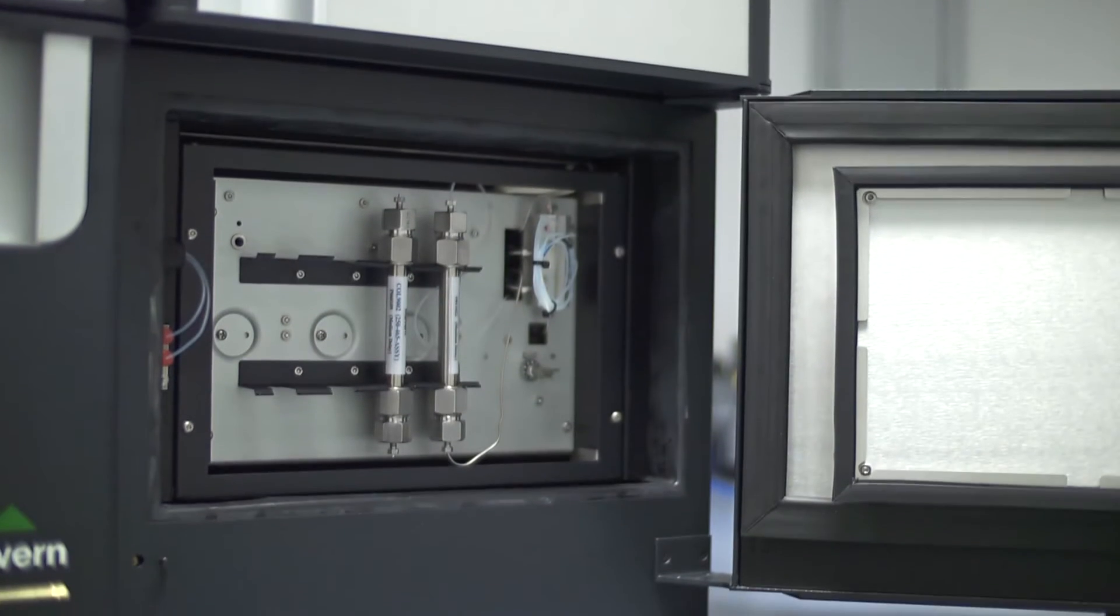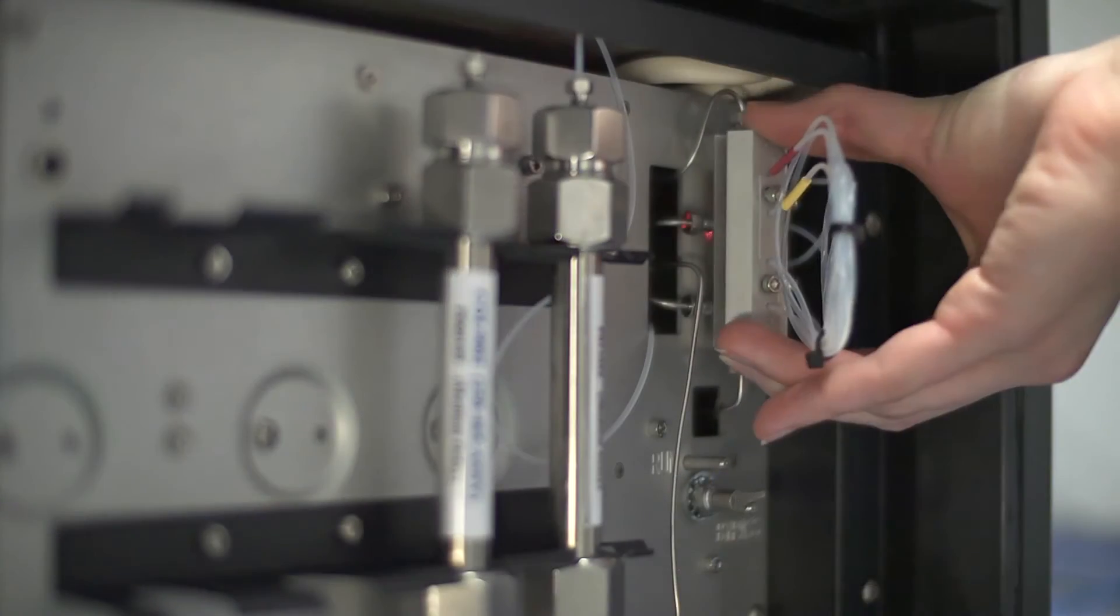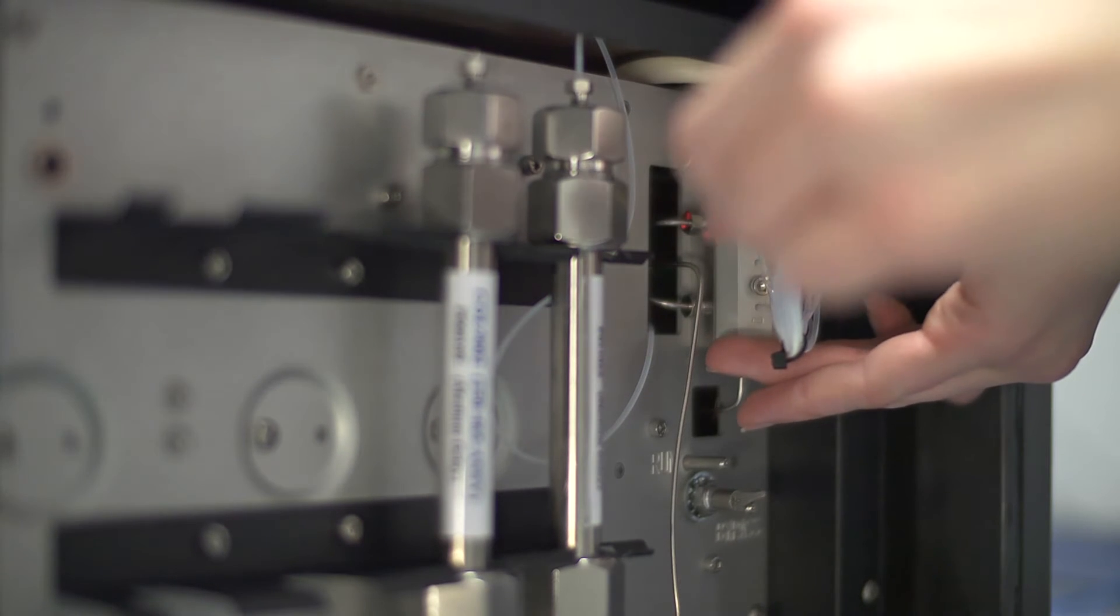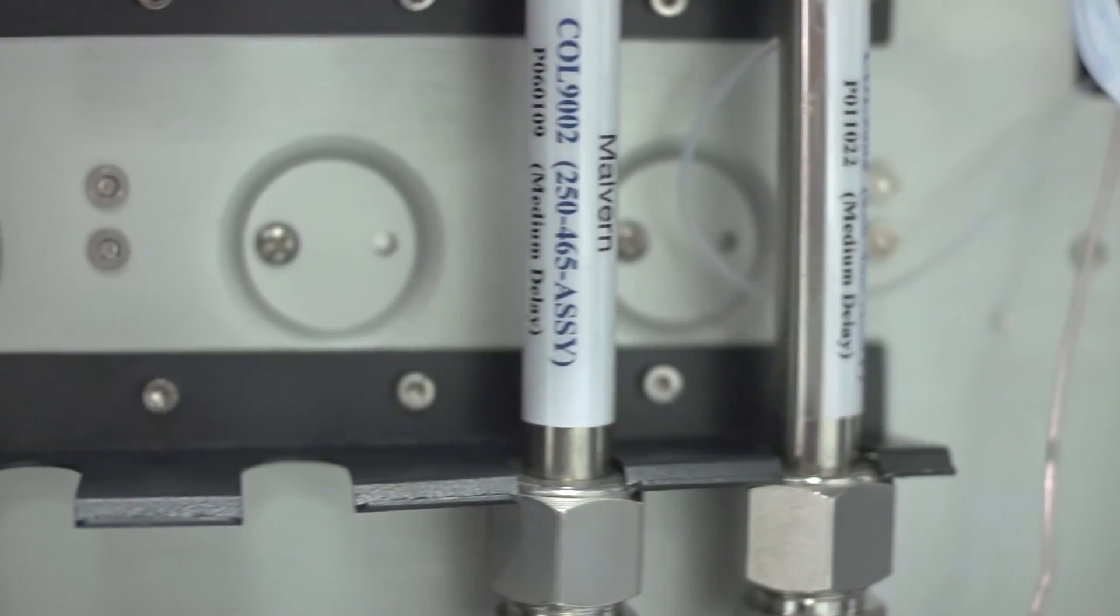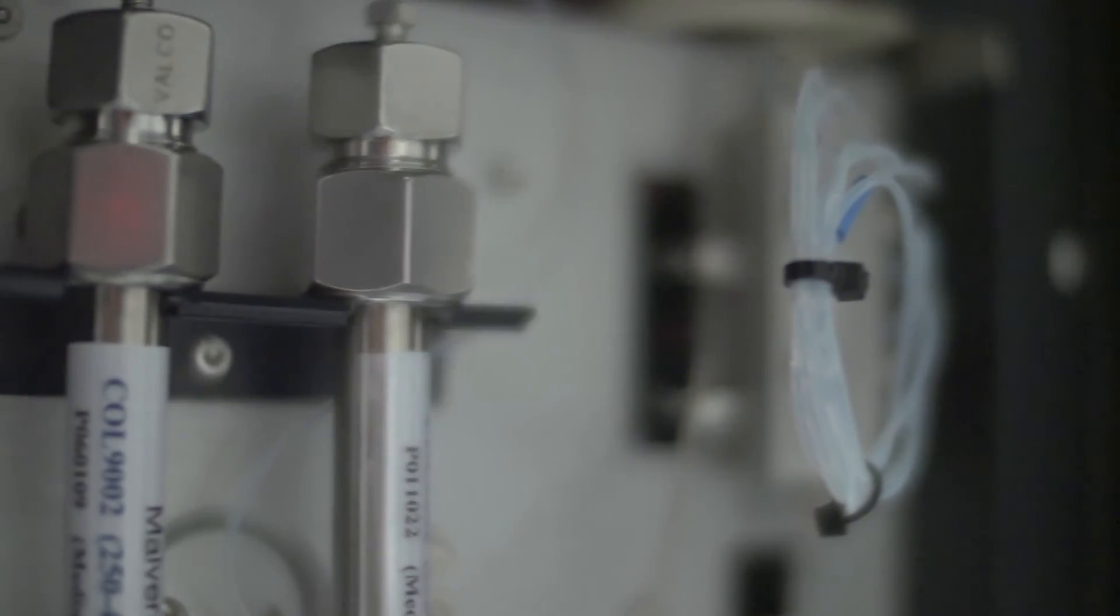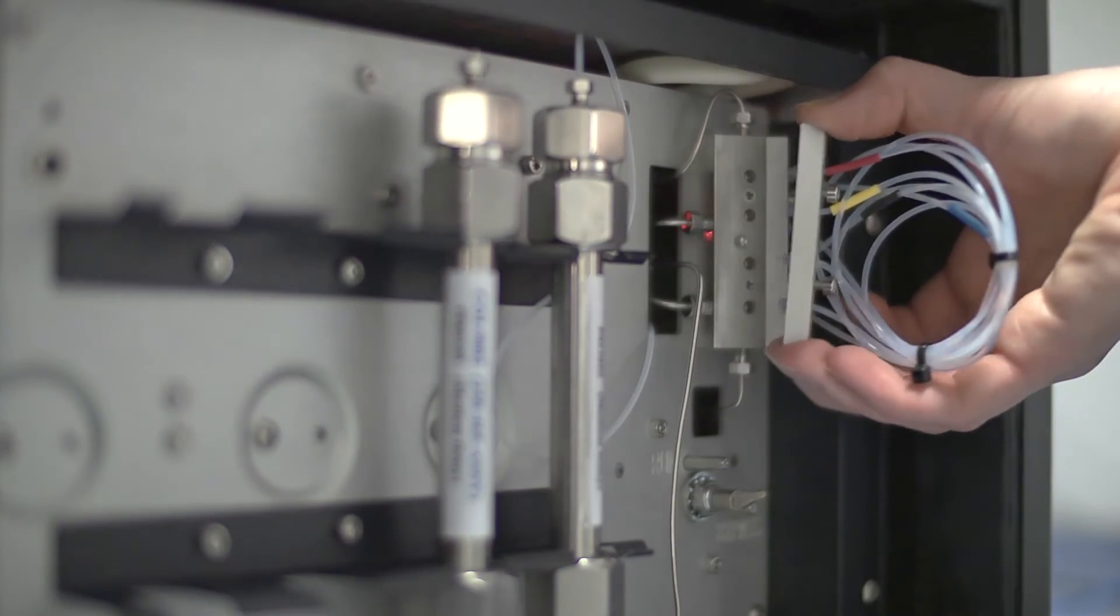With an RI detector that is first in series, inter-detector tubing is minimized to virtually eliminate band broadening and maintain resolution. A differential viscometer with new pressure transducers improves baseline stability, sensitivity, and robustness. Its user-exchangeable bridge boosts instrument productivity and cuts lifetime costs.